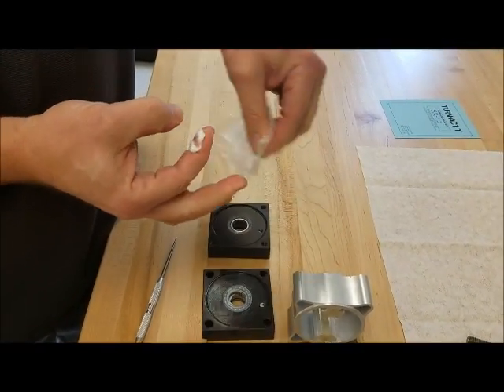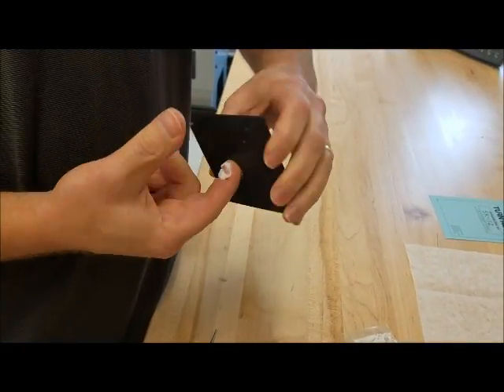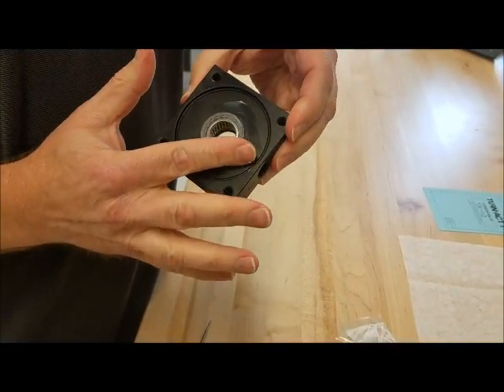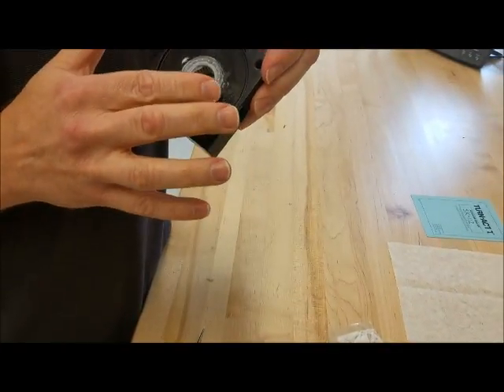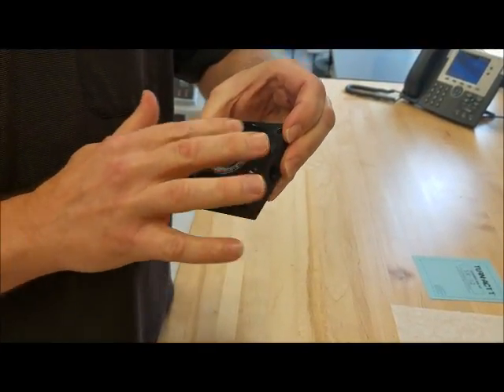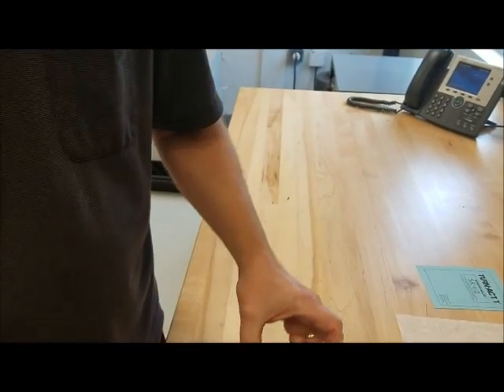Get some more grease and do the other one. The important thing is make sure you fill those holes in the quad ring the best you can because that's where your grease is going to stay and make it a long life.